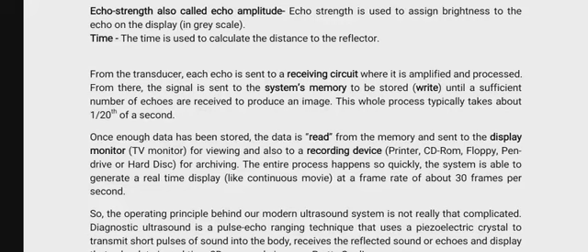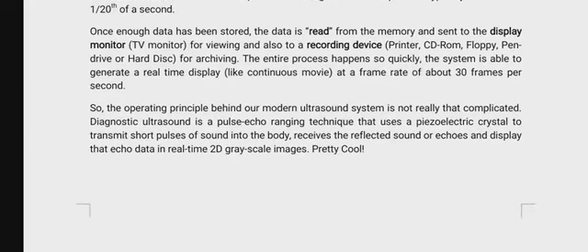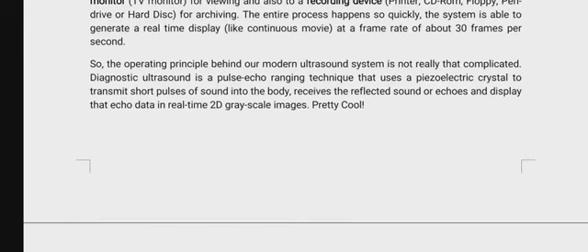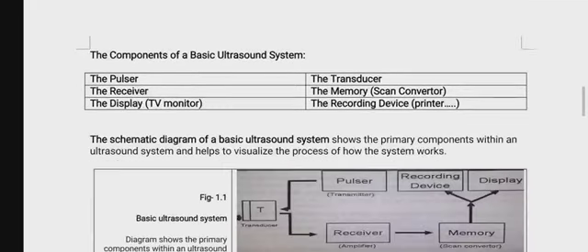The entire process happens so quickly. The system is able to generate a real-time display, like a continuous movie, at a frame rate of about 30 frames per second. So the operating principle behind our modern ultrasound system is not really that complicated. Diagnostic ultrasound is a pulse echo range technique that uses a piezoelectric crystal to transmit short pulses of sound into the body, receives the reflected sound or echo, and displays that echo data in a real-time 2D grayscale image. That's pretty cool. Don't you think so?